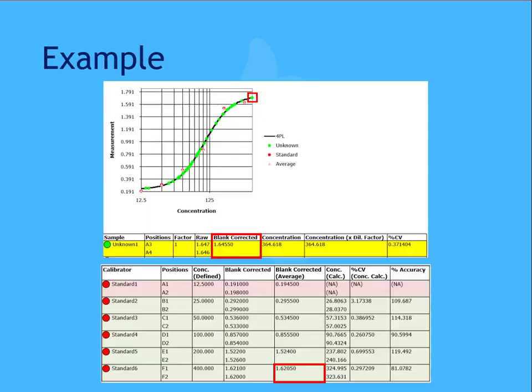Let's look at an example. This is the same sample we discussed in our previous example, where the concentration result is calculable, however, it falls outside the range of the standards. I've diluted this sample times 5, so the dilution factor will be entered as 5. And I've received a new blank-corrected value of 0.688. Now you'll notice 0.688 is not one-fifth of the originally received y-axis value 1.6455, and that's because of the sigmoidal nature of the curve.